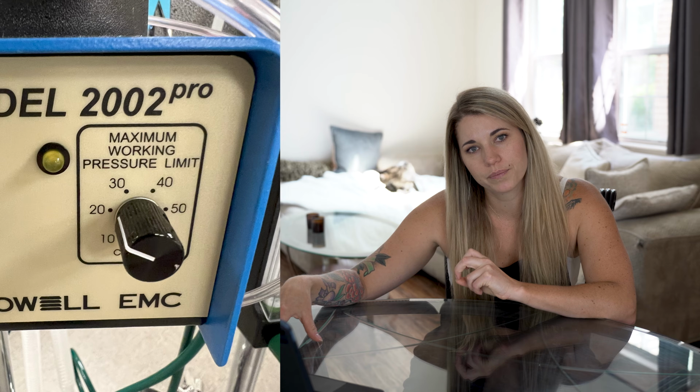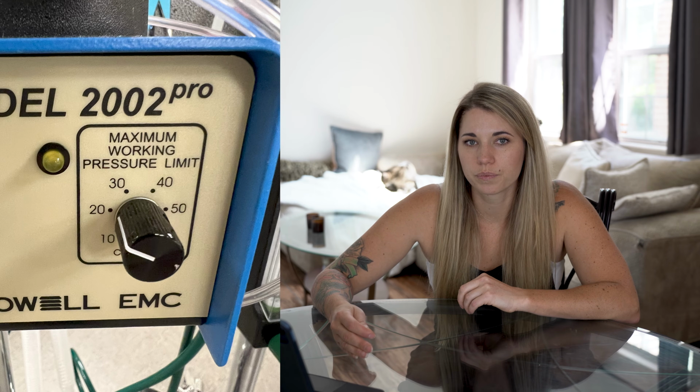The type of controls that your ventilator has is going to vary depending on the brand of ventilator and how modern the ventilator is. In general, ventilators will come with an ability to adjust the volume, which often comes with a micro and macro adjuster, an ability to set the respiratory rate, and then a maximum working pressure limit. The maximum working pressure limit knob allows you to set the peak pressure that the ventilator will deliver a breath to. Some ventilators also come with inspiratory to expiratory ratio controls.